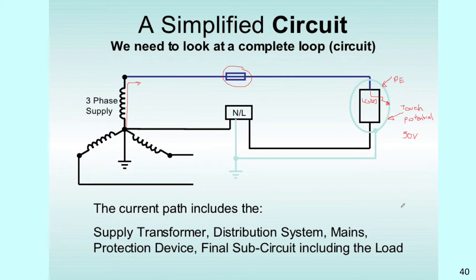Keeping it safe. And if this is well bonded to Earth and our neutral is connected with the MEN. The reality is we would hope that our protective Earth never gets beyond getting up to a couple of volts of touch potential. But 50 is the absolute maximum. So, the current flows through here down into the protective Earth. Through the protective Earth back to the neutral to the MEN. Through the MEN and back to the transformer.